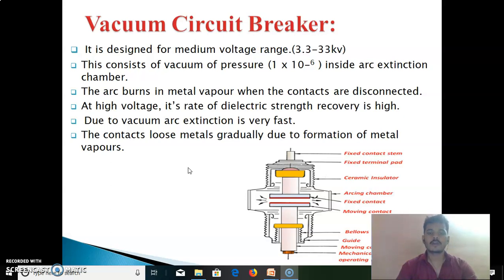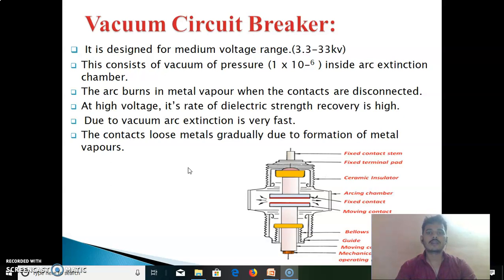The disadvantages of the vacuum circuit breaker: First, it needs an additional surge suppressor in parallel with each phase for interruption of low magnetizing currents in a certain range. Second, it is uneconomical to manufacture vacuum interrupters in small quantities. Third, loss of vacuum due to transit damage or failure makes the entire interruption process useless and it cannot be repaired on site.